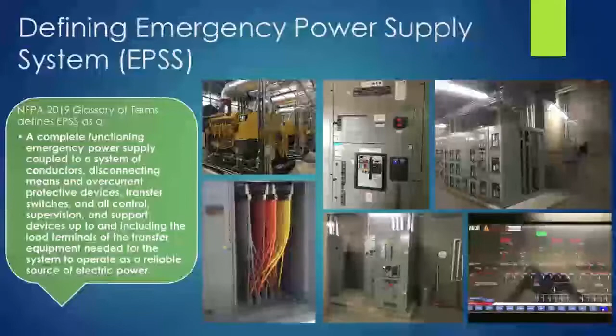So defining, we'll use the NFPA 2019 glossary of terms to define the EPSS system. So it's a complete functioning emergency power supply coupled to a system of conductors, disconnecting means, and overcurrent protective devices, transfer switches, and all the control, supervision, and support devices up to and including the load terminals of the transfer equipment needed for the system to operate as a reliable source of electric power.